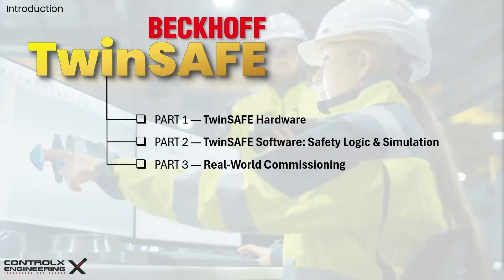Finally, we bring it to life. We'll take our simulated and tested logic and deploy it into a real-world test bench using one of the safety logic terminals from Beckhoff. And we'll use the EL1904 safe inputs and EL2904 safe output terminals. I'll walk you through setting the physical dip switches, mapping safety alias data, and performing the final smoke test with real e-stops and contactors to prove that the system works.